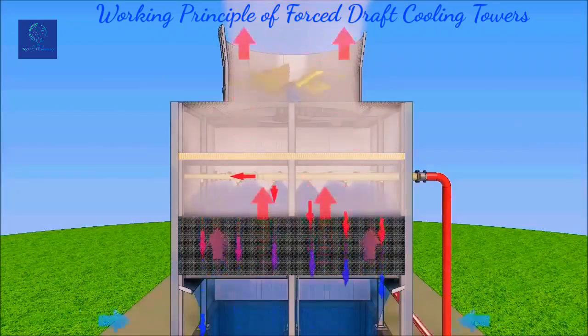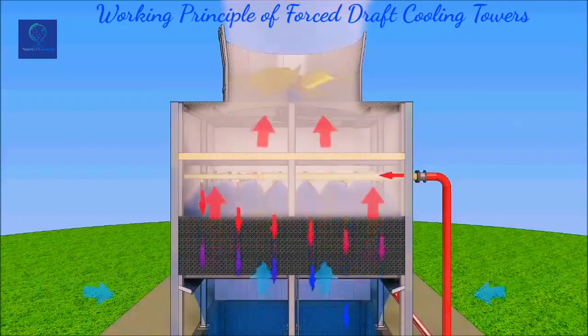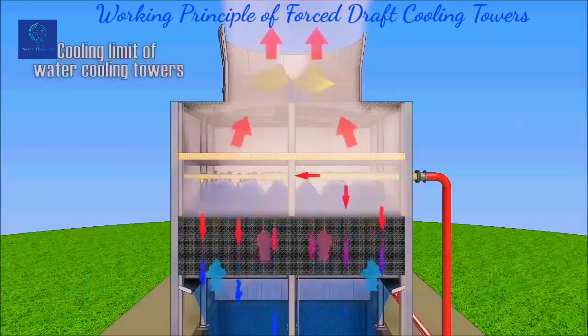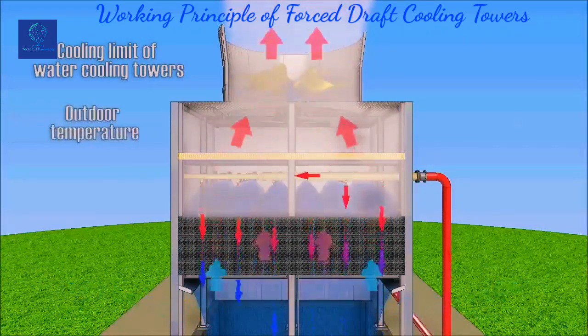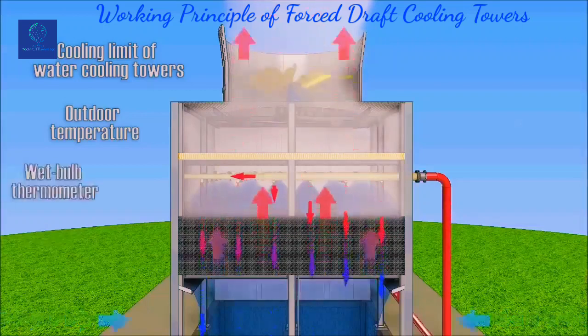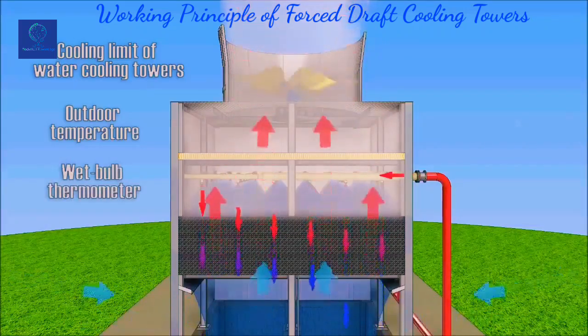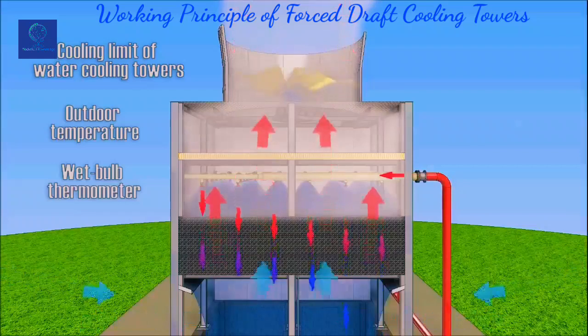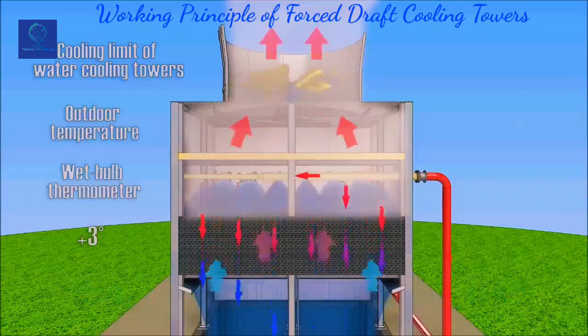Theoretically, assuming ideal conditions with no work losses in converting water to steam, the cooling limit in a cooling tower is the outside air wet bulb temperature. In practice, the limit of cooling is the wet bulb temperature plus 3 degrees Celsius.